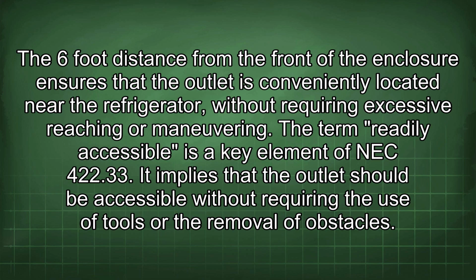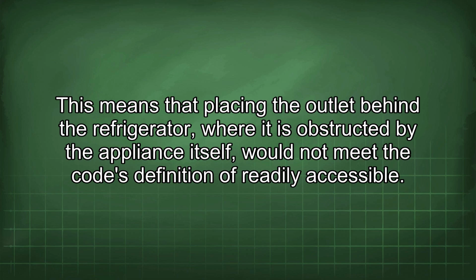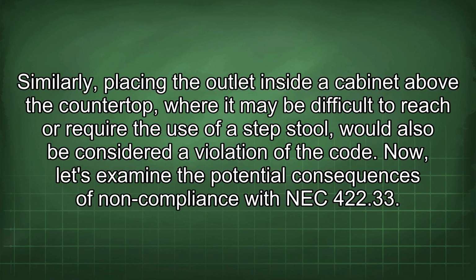The term readily accessible is a key element of NEC 422.33. It implies that the outlet should be accessible without requiring the use of tools or the removal of obstacles. This means that placing the outlet behind the refrigerator, where it is obstructed by the appliance itself, would not meet the code's definition of readily accessible. Similarly, placing the outlet inside a cabinet above the countertop, where it may be difficult to reach or require the use of a step stool, would also be considered a violation of the code.